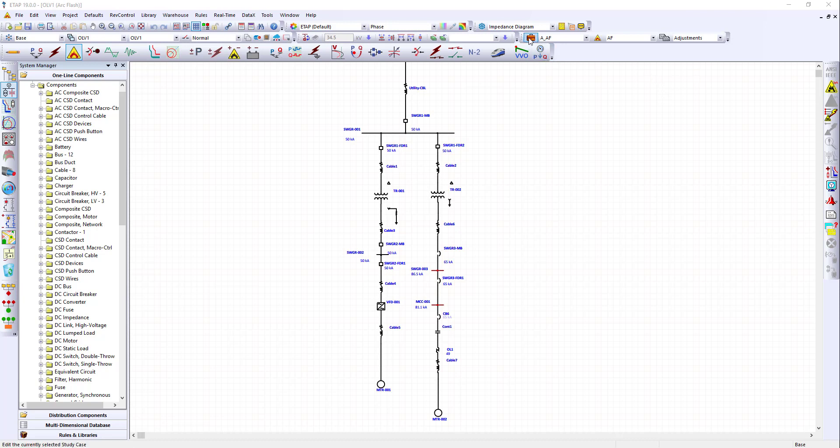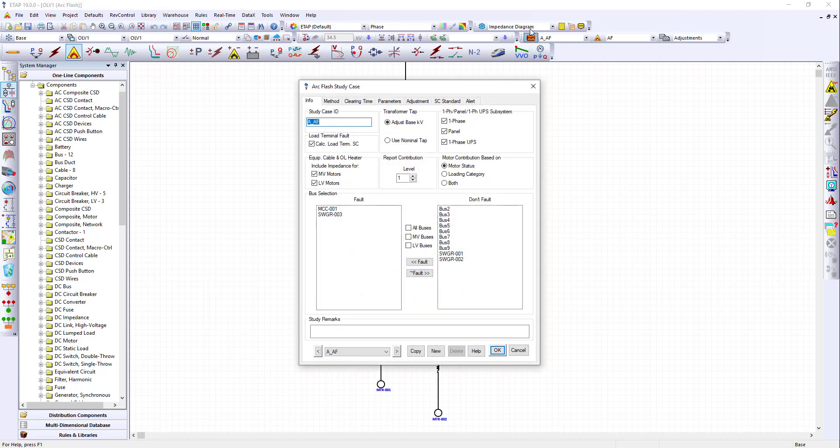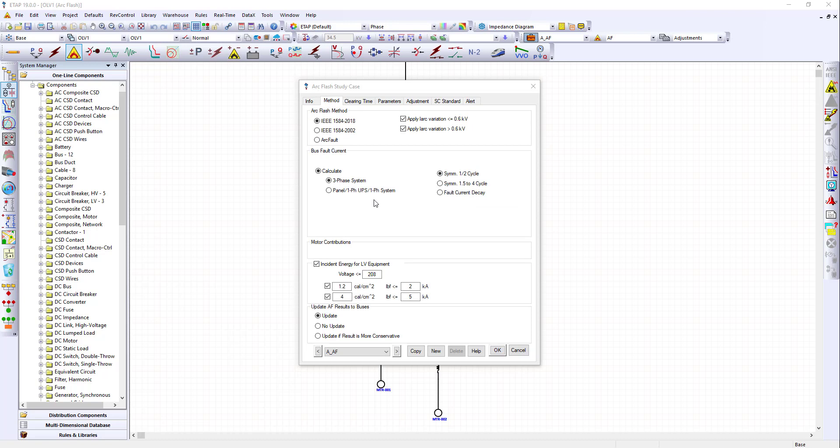Just like the short circuit study case, we need to fault some buses and make the appropriate selections on this page. Next, we need to decide which standard we're going to choose. In this example, I've chosen the latest IEEE 1584 standard 2018. IEEE 1584 is undergoing revisions on how to calculate the incident energy based on the construction of the electrical equipment. And so my friend, you as the Arc Flash electrical engineer, need to know what is the construction of this equipment.